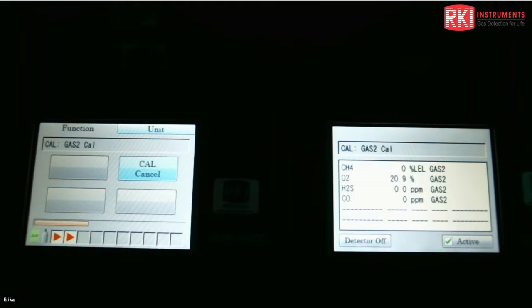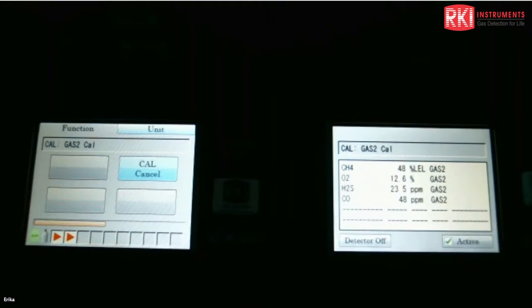Yeah, only the master dock, which is the one on the far left, has the function and the unit buttons. The function button shows the master dock settings and controls, and the unit button just shows what's going on with the instrument that's in that particular dock. So right now it's at gas 2 Cal, which is the standard 4 gas, which you can see on here. It's reading that. So that's the answer to your question, Dwayne. It will automatically apply the correct gases to the correct instrument as it goes through the calibration, and it'll skip the ones that don't apply to a particular instrument.